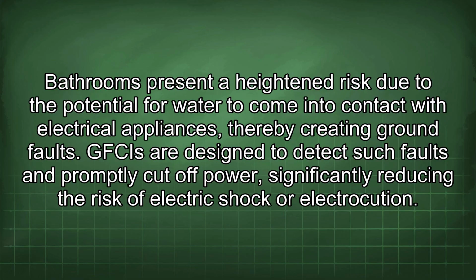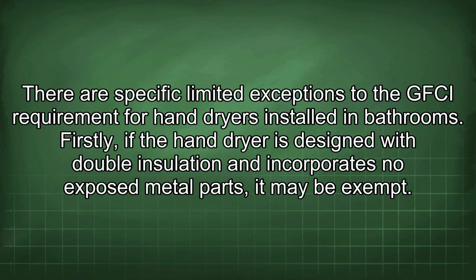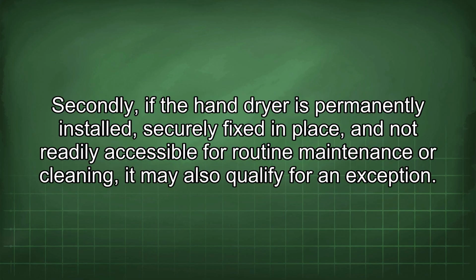There are specific limited exceptions to the GFCI requirement for hand dryers installed in bathrooms. Firstly, if the hand dryer is designed with double insulation and incorporates no exposed metal parts, it may be exempt. Secondly, if the hand dryer is permanently installed, securely fixed in place, and not readily accessible for routine maintenance or cleaning, it may also qualify for an exception.